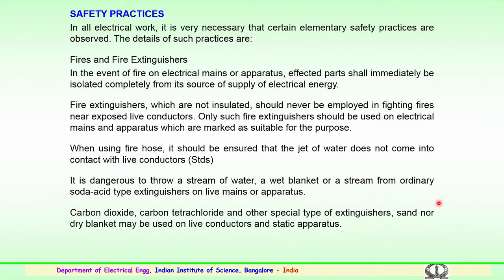These fire extinguishers, which are mainly not insulated, should never be employed in fighting fires, particularly near exposed live conductors. Only such extinguishers should be used on the electrical mains and apparatus which are suitably marked for this purpose. Also, during the use of a fire hose, it should be ensured that the jet of water does not come in contact with the live conductors. So, this again could electrocute the personnel who is operating the fire hose.